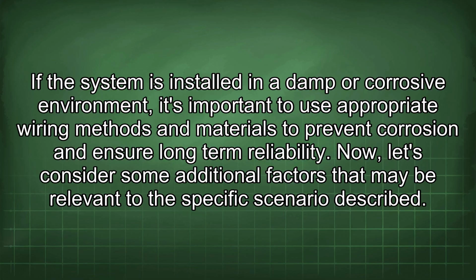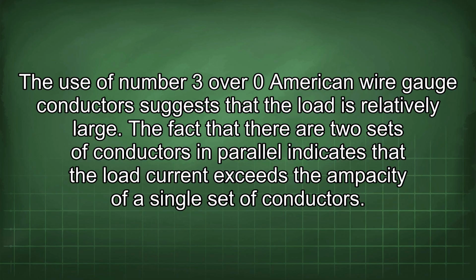Now let's consider some additional factors that may be relevant to the specific scenario described. The use of number 3/0 American wire gauge conductors suggests that the load is relatively large. The fact that there are two sets of conductors in parallel indicates that the load current exceeds the ampacity of a single set of conductors.